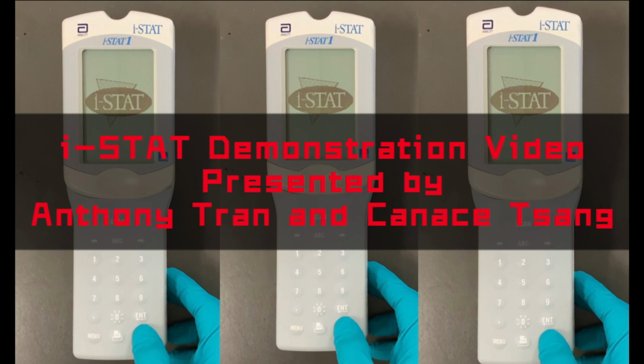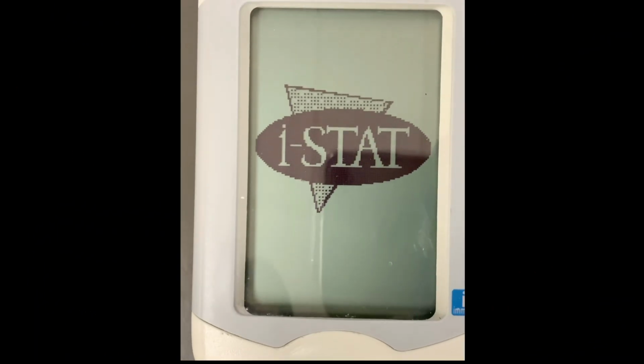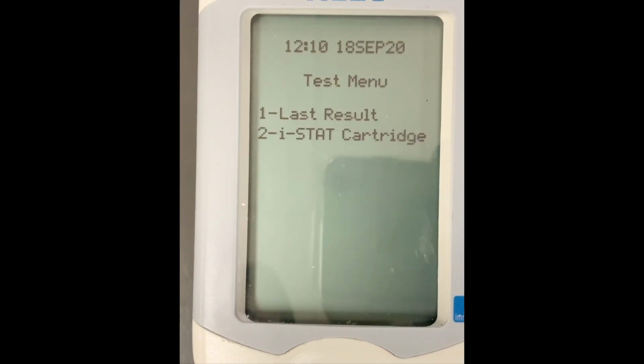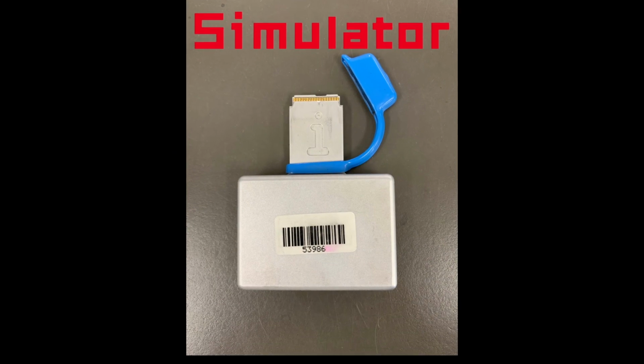The iStat incorporates comprehensive components needed to perform blood analysis at the point of care. This analyzes blood gases, electrolytes, chemistries, and hematocrit levels. When you first turn on the iStat, it will display a test menu and you only have two options available at this point. However, in order to use the iStat, a simulator is required for sample calibration every 24 hours before patient testing can be conducted.